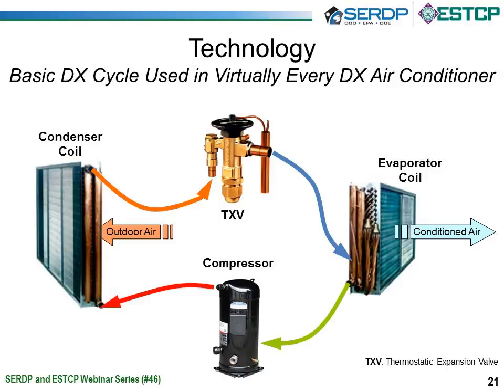The compressor compresses the refrigerant vapor that comes from the evaporator coil, which is, let's say, mostly vapor, and it compresses it to a high pressure, high temperature gas, which will be the red line, where it goes to the condenser coil. In the condenser coil, outdoor air flows through the coil and removes the heat as the refrigerant condenses from a high pressure gas to a high pressure liquid.